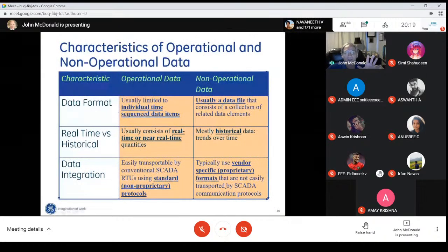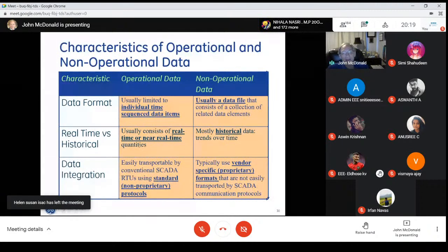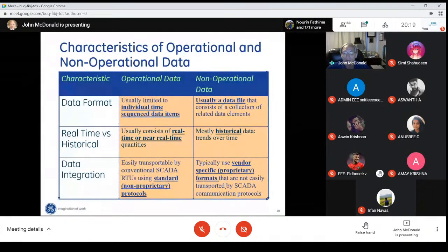So operational data is typically individual time sequence data items, and it's typically a time series of points at the scan rate of the SCADA master. The non-operational data is points or a file. The operational data is real-time or near real-time. Non-operational is typically historical, a trend over time. Okay, operational data we communicate using standard communication protocols, non-proprietary, and non-operational data is points or a file. And if it's a file, we may need the vendor-specific proprietary format to access that file, okay?